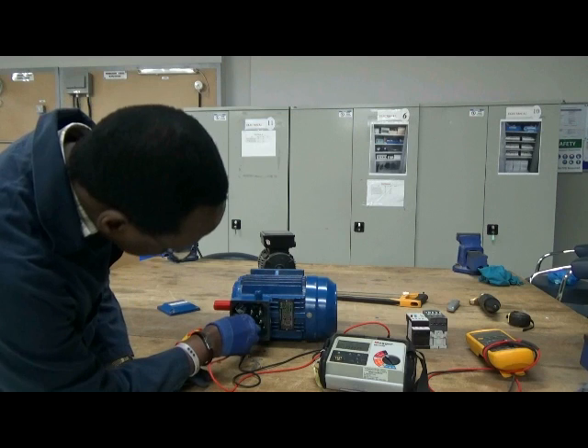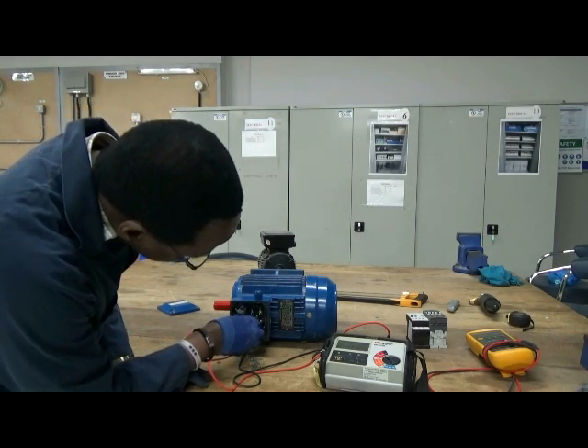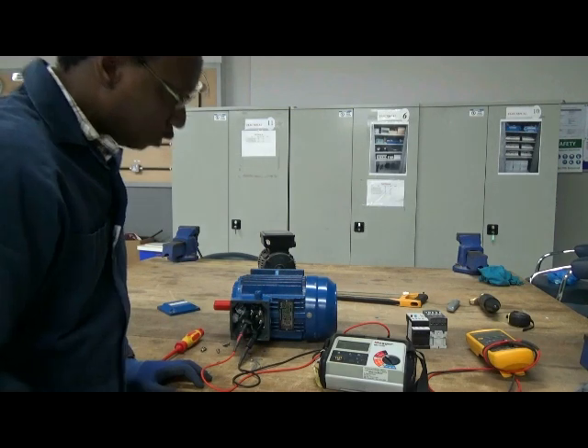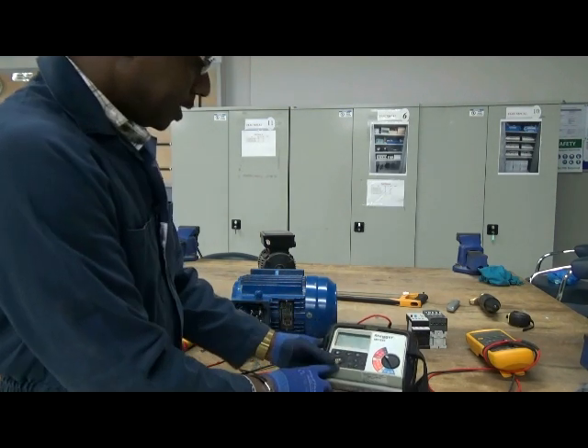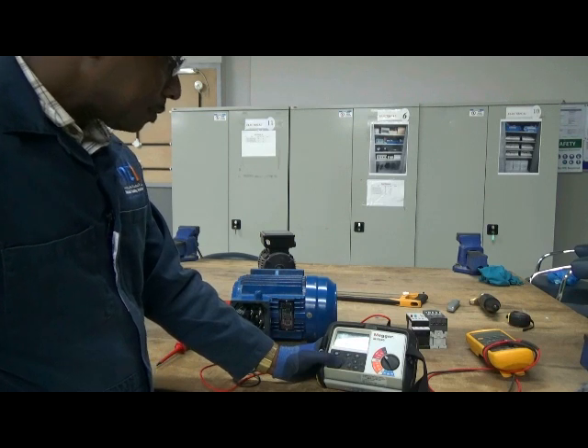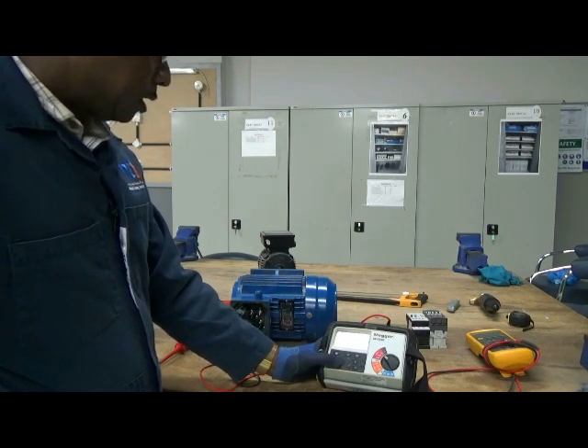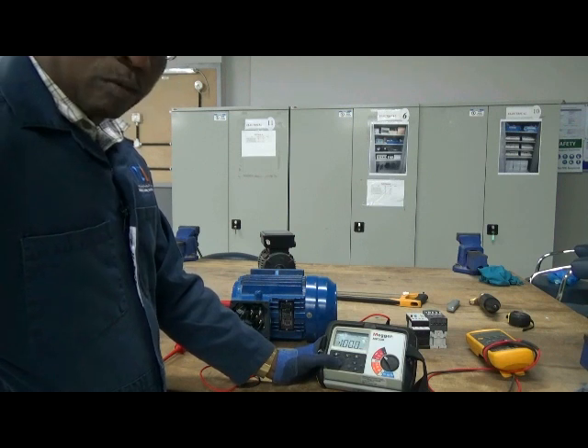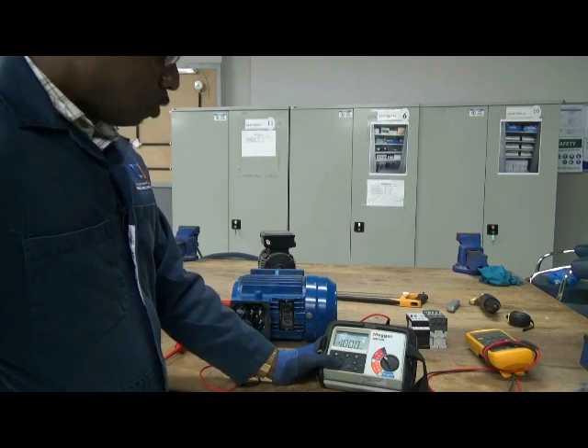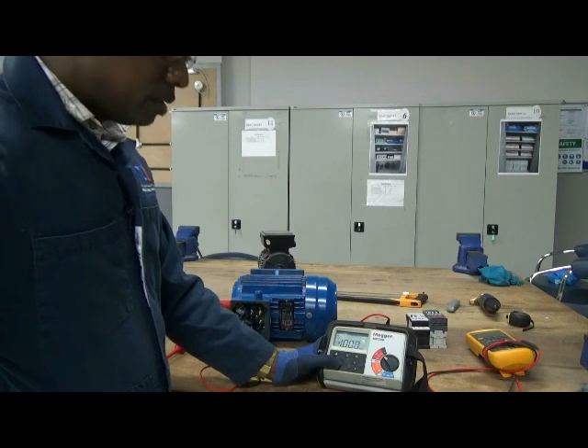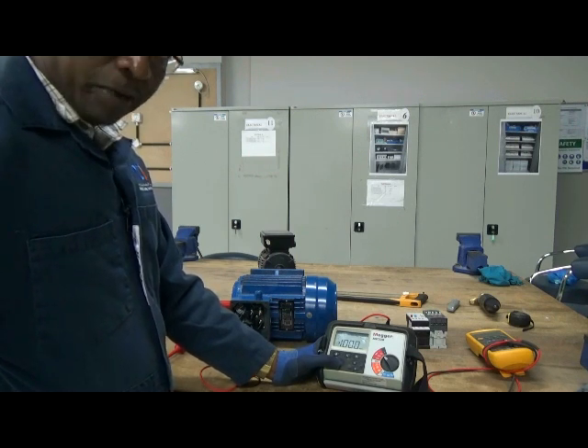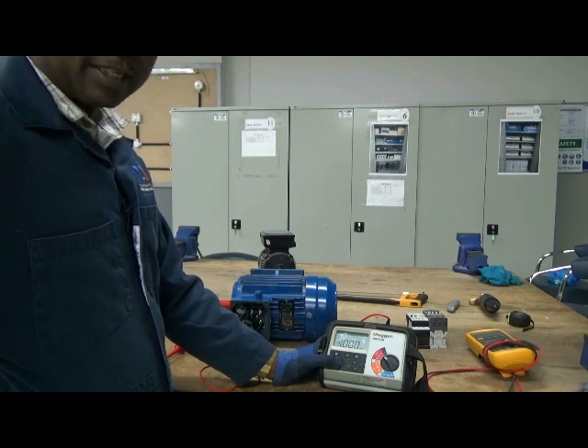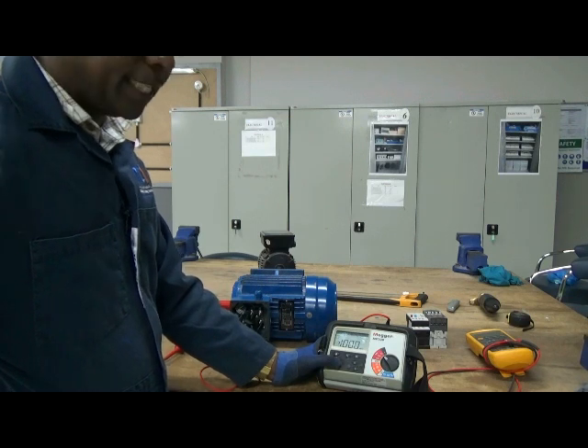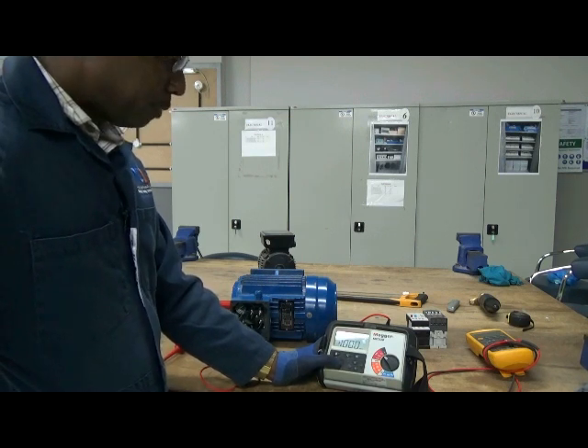So I'll go on to the next winding. I'll leave the first point where it is and then connect it to the second one and see again if there's a very high resistance. Once again, I get bigger than 1,000 mega ohms, which means 1,000 million ohms. Very, very high resistance. And that is acceptable because it is above 1 mega ohm according to the IET regulations, which we follow. Those are the British standards, which we follow also here in Oman.